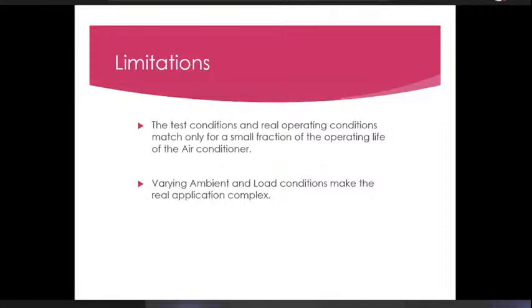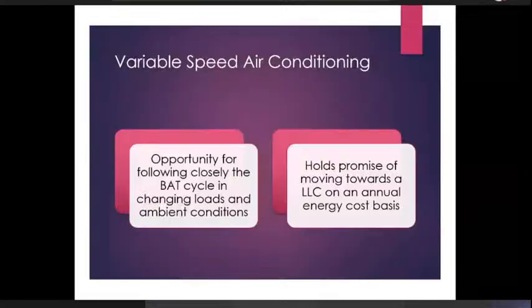However, variable speed air conditioning offers us these opportunities. So it's an opportunity for closely following the best available technology cycle in changing load scenarios and changing ambient conditions. And also it helps us move towards a life cycle cost analysis on annual energy cost basis. So even if we put aside the sustainability advantage and just look at energy costs, a variable system would promise a lower overall energy cost versus a fixed speed system because of the opportunity at part load conditions.